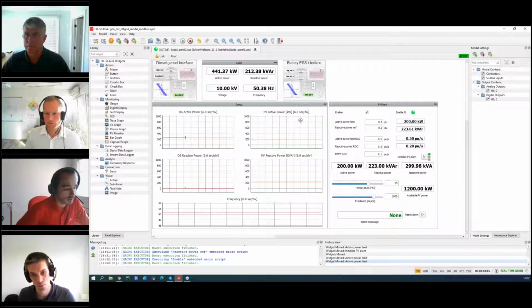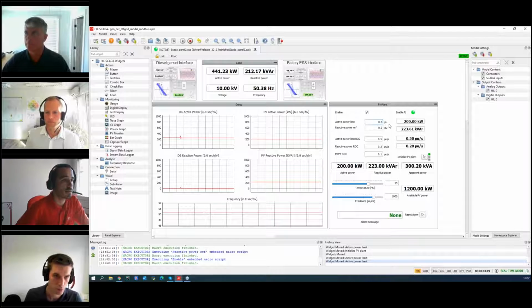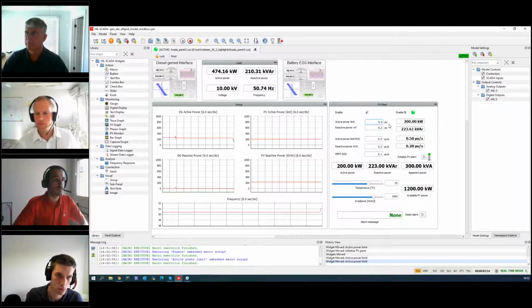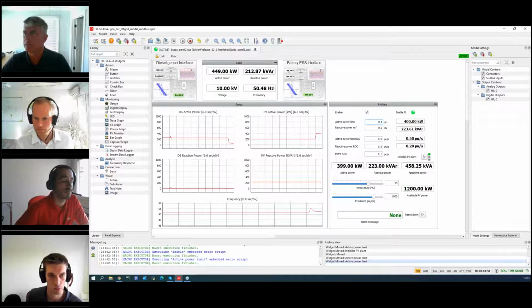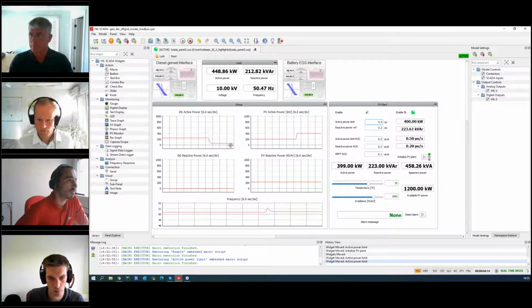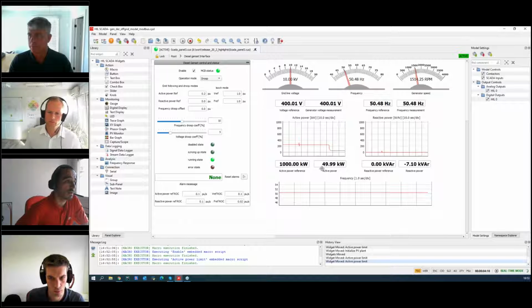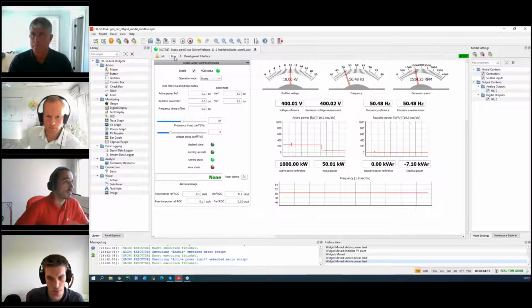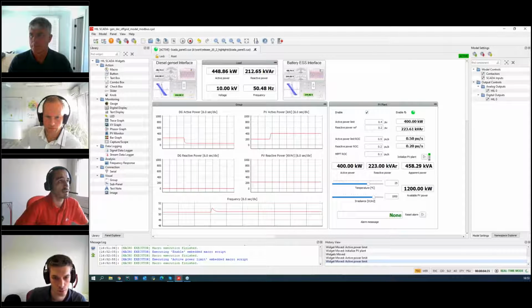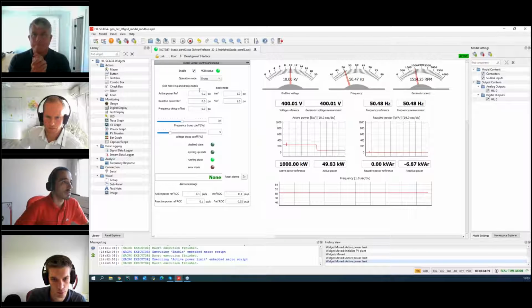Now what will be interesting is to increase the PV power in the system a little, because here you can see that the available power from the PV is 1.2 megawatts. So we have plenty of PV power at our disposal. We will increase the active power limit, and now the power from the diesel genset decreased to around 50 kilowatts. So this diesel genset is now operating in a low power regime, in which it is least efficient. Let's say this power of 50 kilowatts we can transfer to the battery, and at this point we just disengage the diesel genset.